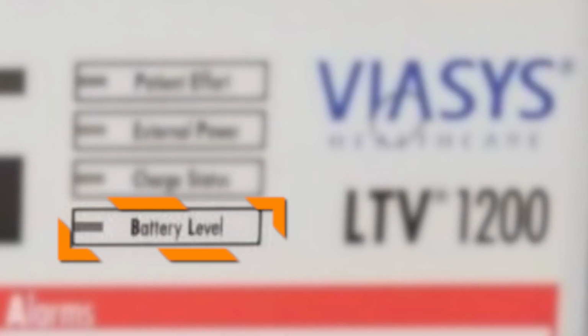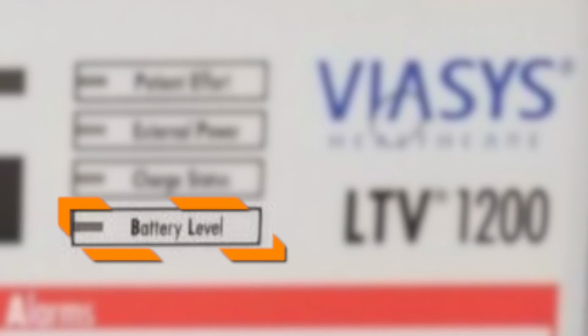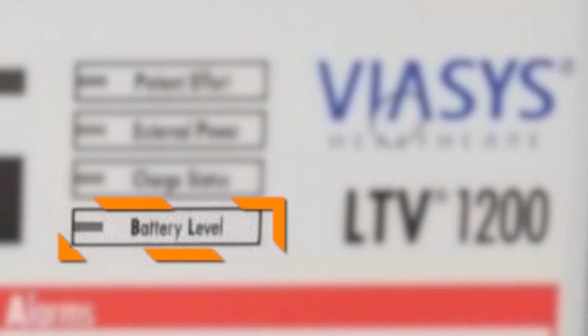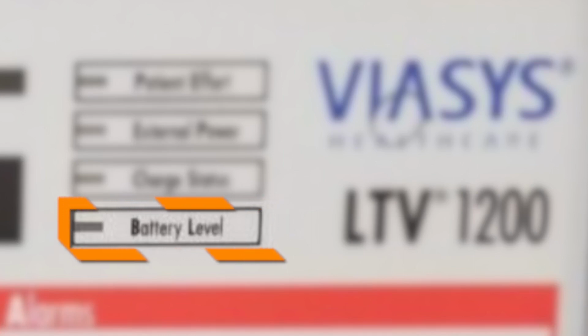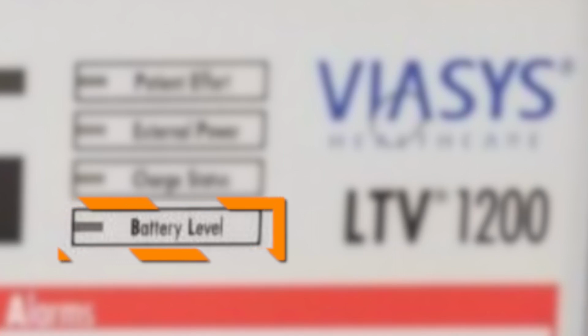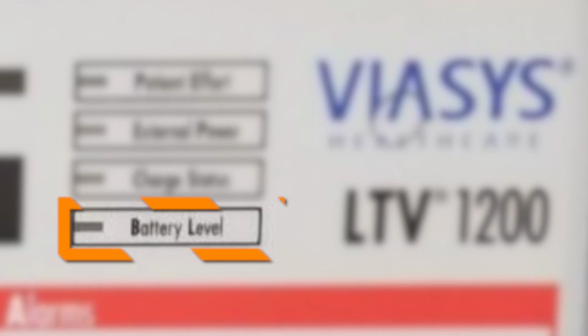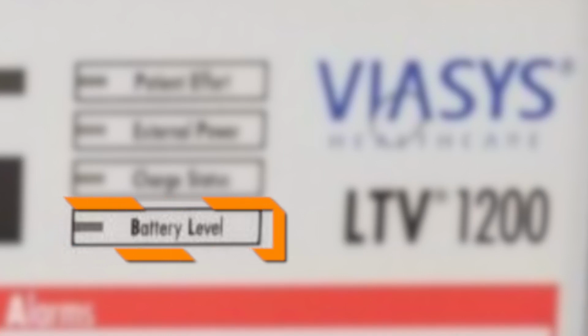Battery level. The battery level indicator shows the level of available internal battery power while running from the internal battery. If it's green, it has about 45 minutes. When it's amber, that means the battery is low, and it has only about 10 minutes. When it's red, the internal battery is critically low and may have less than 5 minutes of power remaining. If the LED is not lit, that means the ventilator is running on AC or external battery.